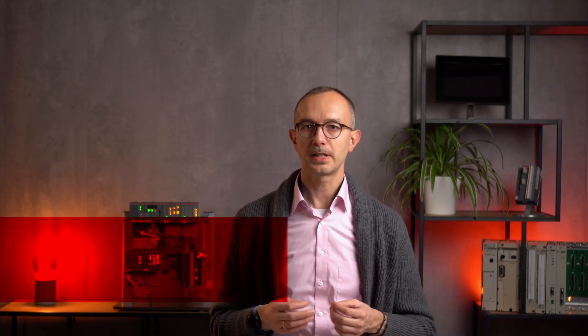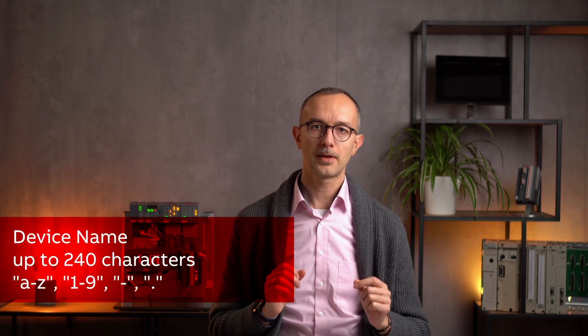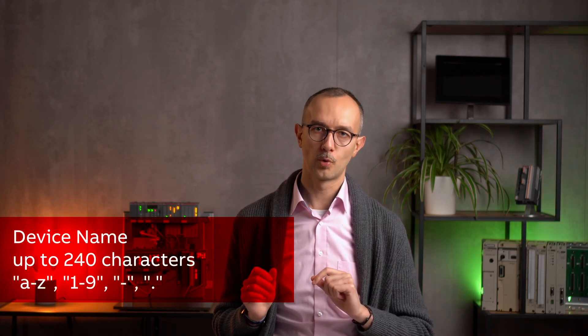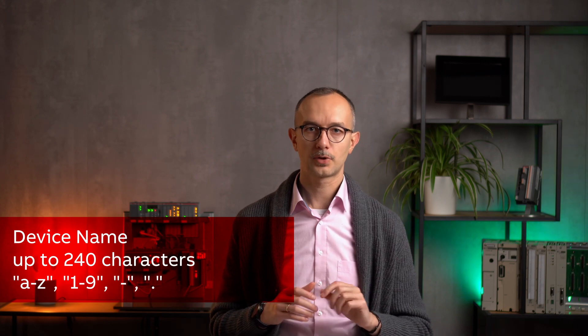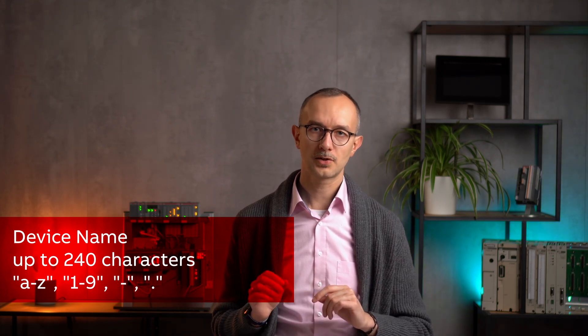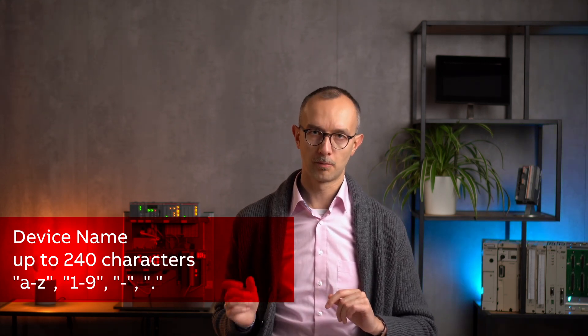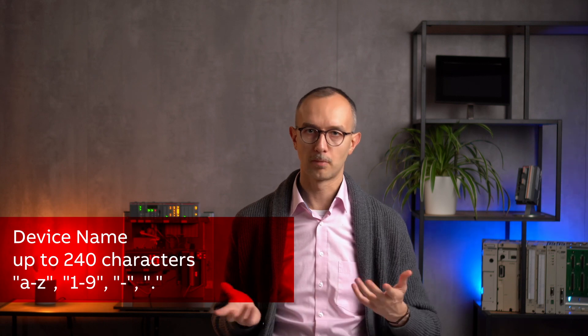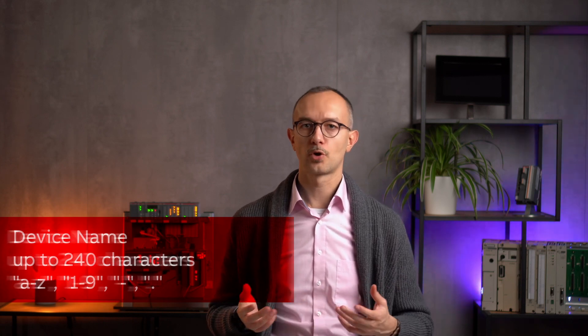Important thing to understand is that along with an IP address, PROFINET protocol also uses I.O. device name to run the communication. Device name is a text string with a length up to 240 characters. Allowed characters are lowercase latin letters, numbers, hyphen, minus, and fullstop character.